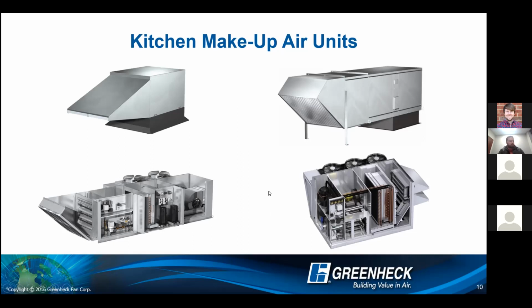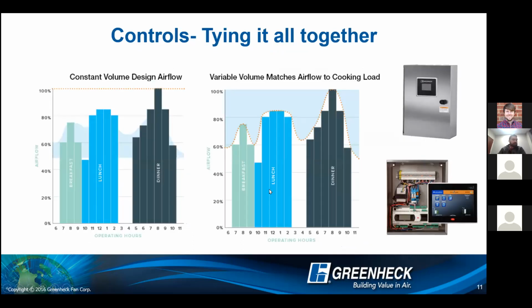Moving on to controls. So here's where we're going to slow down a little bit and talk more specifically about controls. What does code call for? What is the right design criteria when doing controls? So no matter the manufacturer, you're going to have two types of controls out in the market. You're going to have a constant volume control center or a variable volume control center. The control center will be the brains of this system. So it's going to tie those exhaust fans and those makeup air fans together.